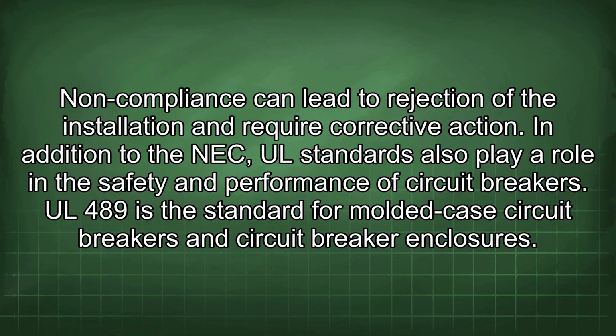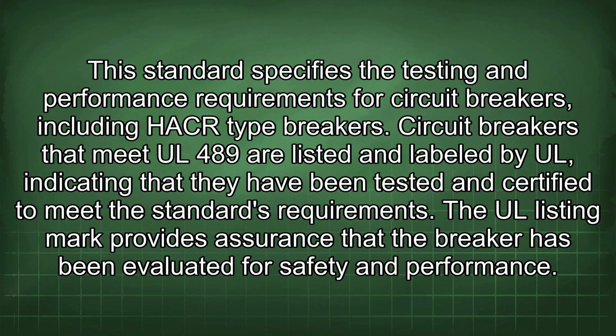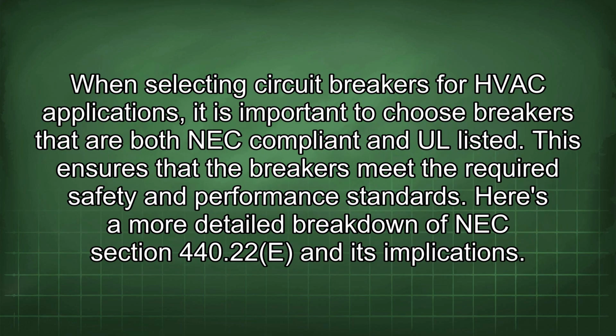UL standards also play a role in the safety and performance of circuit breakers. UL 489 is the standard for molded case circuit breakers and circuit breaker enclosures. This standard specifies the testing and performance requirements for circuit breakers, including HACR-type breakers. Circuit breakers that meet UL 489 are listed and labeled by UL, indicating that they have been tested and certified to meet the standard's requirements. The UL listing mark provides assurance that the breaker has been evaluated for safety and performance. When selecting circuit breakers for HVAC applications, it is important to choose breakers that are both NEC compliant and UL listed. This ensures that the breakers meet the required safety and performance standards.